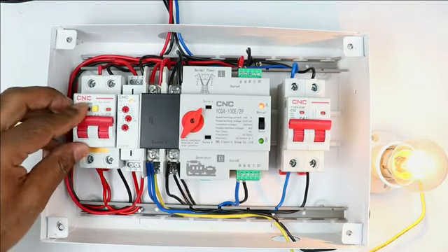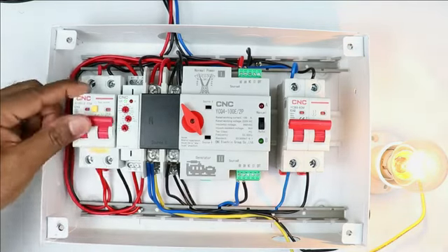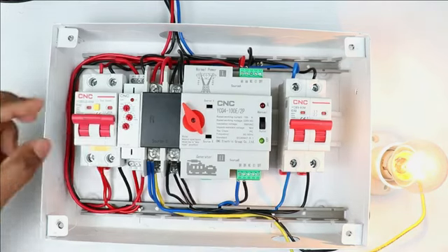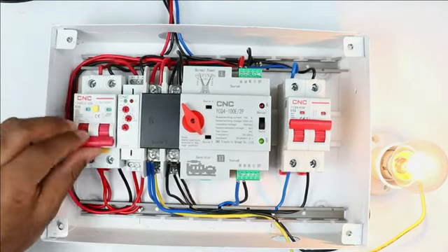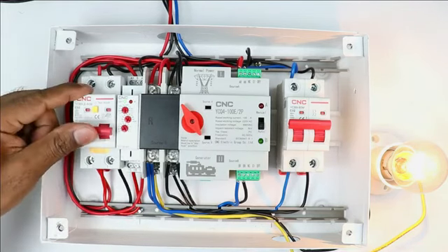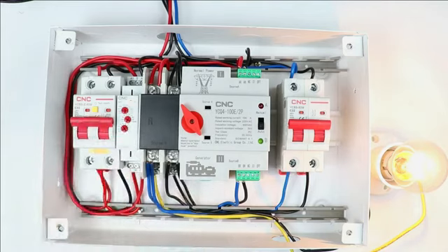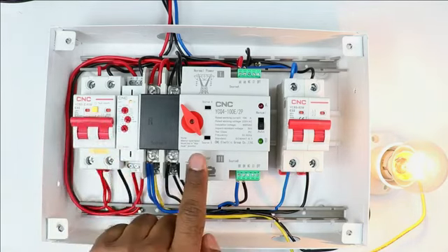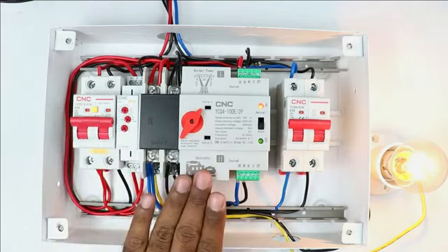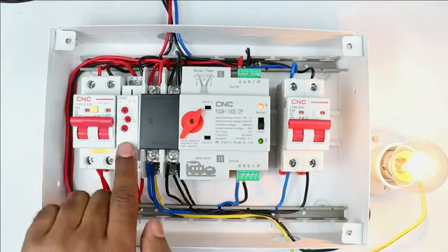Point is, when main power supply fails, the changeover will take place instantly, but when main power supply comes back, this changeover will not take place instantly. It will wait to check whether your main supply is not failing again. If your main supply didn't fail again, then after the time programmed in the timer, this changeover will take place automatically. You saw how the changeover was done. So finally, I solved the problem with ATS by connecting a timer in between.